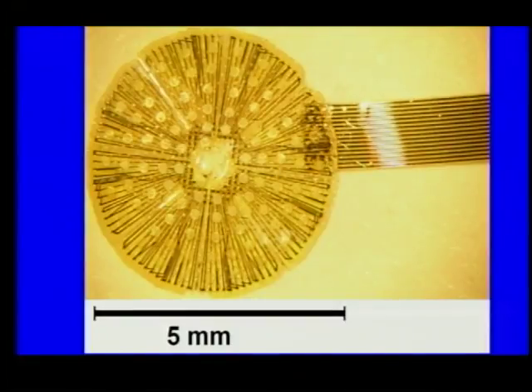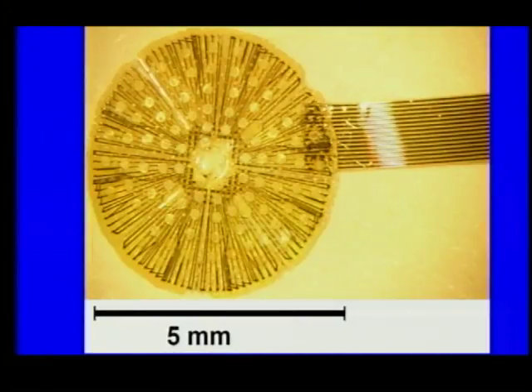So let me show you how extreme we've pushed it. If you want someone to navigate safely through an unfamiliar area, you'd like to give them a fairly wide field of view, right? If you have a very small field of view, you're constantly having to search. So we made this 5 mm diameter electrode array. This one happens to have 100 electrodes. You can see the round electrodes, each one hardwired to the computer chip. So this device, theoretically, if we put it in humans, would allow us to provide more than 20 degrees of visual field. It's huge. Now, there would be no way of securing this on the epiretinal surface, right? Because you'd have to have tacks or glues all the way around. It's just not practical. But boy, on the subretinal side, here you see it implanted in a pig.